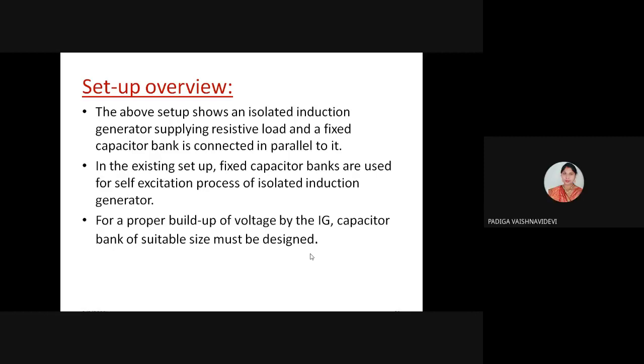When the machine draws reactive power, it further starts building up the EMF. When the machine further builds EMF, the capacitor voltage further increases. It's a one-to-one arrangement, and slowly the machine will build the EMF to the rated value. So the proper buildup of voltage by the induction generator depends mainly on the value of the capacitance, so a suitable size of capacitor bank must be designed.